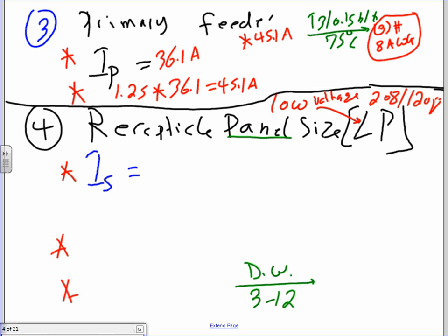You need three conductors. I don't need a neutral. I'm feeding a delta. Delta has only three wires. Cool? Any comments, guys? Any questions about that? Does it make sense? Yes? No? All right. Let's go to the receptacle panel sizing.